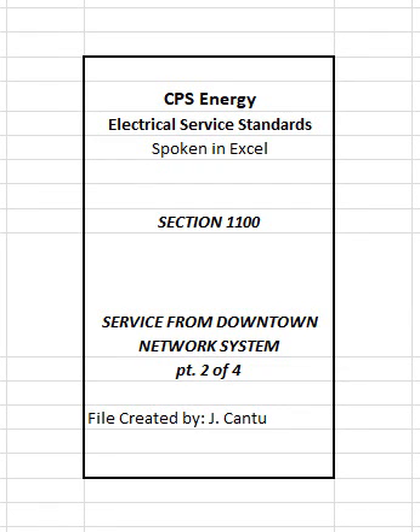1103 One customer-built transformer vaults or rooms. The customer's load requirements will determine the transformer vault or room size. Typical transformer vault size is 32 feet L x 15 feet W x 12 feet H, and 38 feet L x 20 feet W x 12 feet H, for service voltages 208Y/120 volt and 480Y/277 volt respectively. Customer shall provide sealed engineered drawings of the proposed vault or room per CPS Energy requirements.